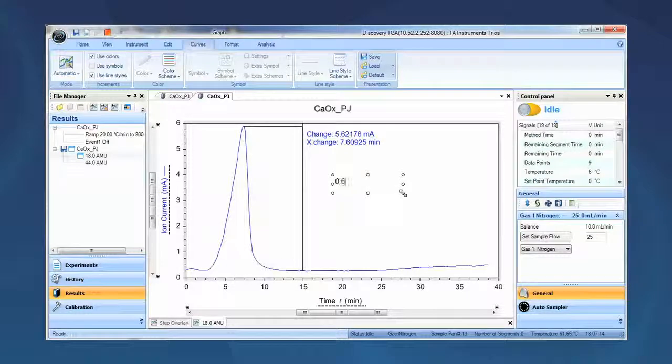Ideally, I'd like to record and track this value over time on a regular basis, possibly in a notebook or a spreadsheet. Maybe I'd perform this analysis once a week or so and verify that I'm getting this number, roughly 0.7 or so. This will be unique for your instrument. You may get a little less or a little more, depending. The time to check would be after installation or maybe after a service call. If the value is decreasing significantly, say by half or an order of magnitude, it's probably time for service to the instrument. Maybe I need to clean the TGA, do a system bake out of the Discovery Mass Spec, check the filament condition by simply switching to the spare filament and repeating the test.